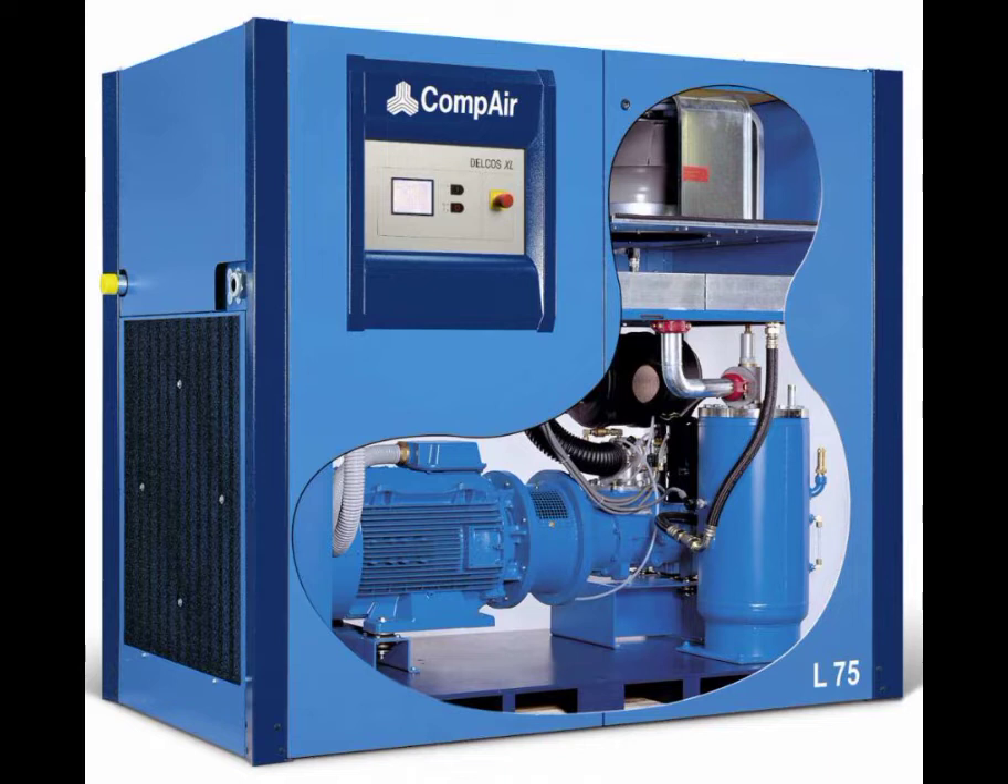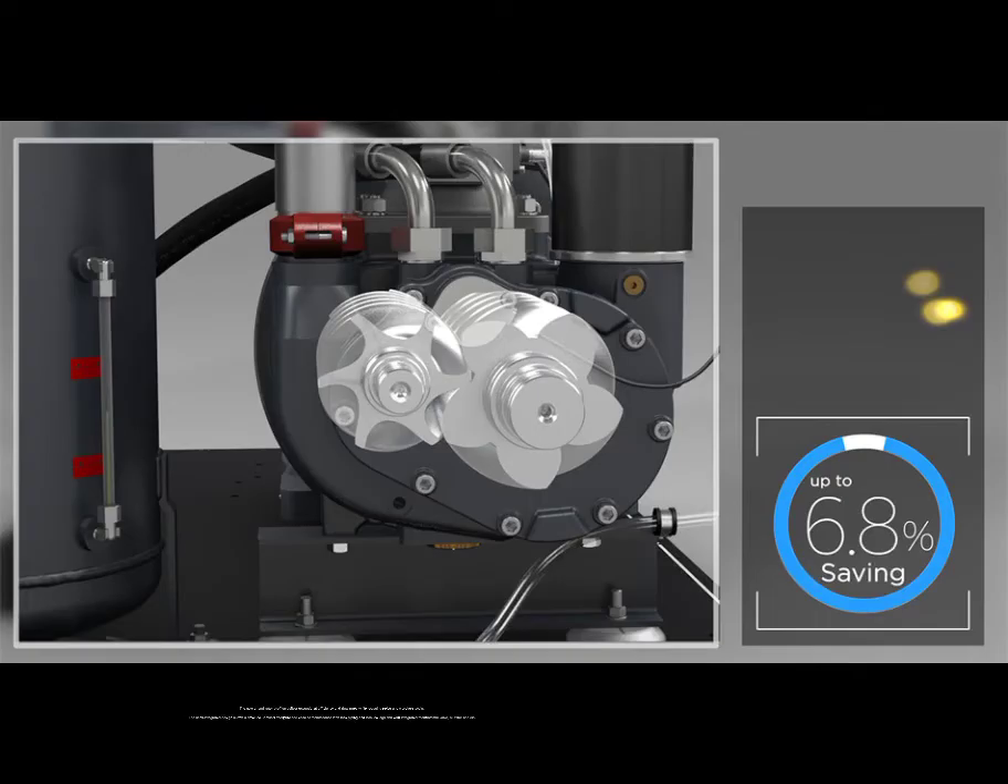Redesigned GD6 semi-integrated airend with better performance that can reach 5–6% improvement at high speed and 3–8% efficiency improvement for the complete package. The new airend rotor profiles deliver exceptional efficiency and flow rates while reducing noise and vibration levels. The semi-integrated design allows a small compressor footprint and ease of maintenance with less piping and less leakage risk, with integrated thermostatic valve, oil filter, and disc.